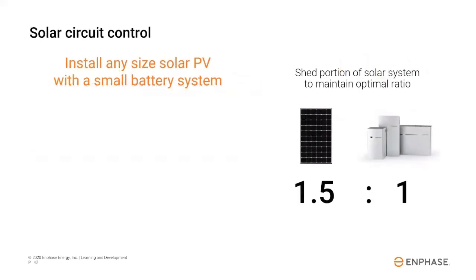The next feature we'll talk about is solar circuit control. This is done essentially the same way that load control is done. And the advantage is that you can install any size solar PV system with a small battery system. As you might be familiar with other systems, there's a maximum amount of solar power that you can connect to a given battery, because during a grid outage, that battery needs to be able to absorb all the power that's coming down from the PV system. If there's too much power, it can overwhelm the battery inverters and cause instability and blackouts. Various manufacturers have different guidelines. Our recommendation is a 1.5 to 1 ratio of solar AC power to storage AC power for maximum stability.